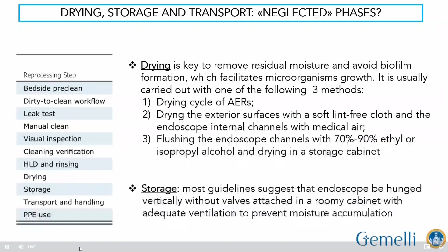It can be carried out with 3 different methods. In large volume centers, usually the drying cycle is carried out by automatic endoscope reprocessors. But as you can see in points 2 and 3, in smaller centers, manual drying can also be done. After drying, ideally, the scope should be stored, and most guidelines suggest that the endoscopes be hung vertically without valves attached in a roomy cabinet with adequate ventilation to prevent moisture accumulation.